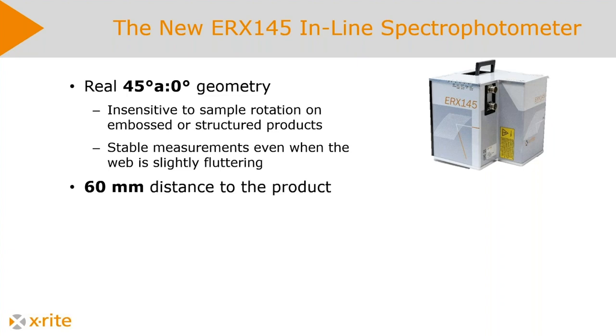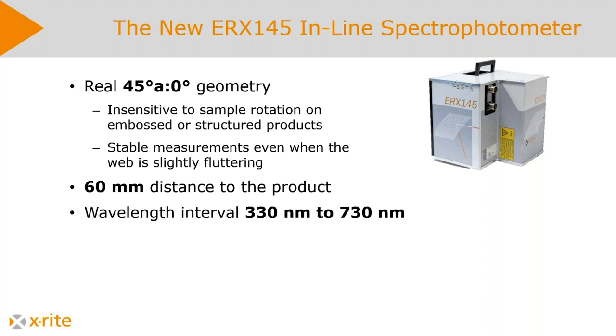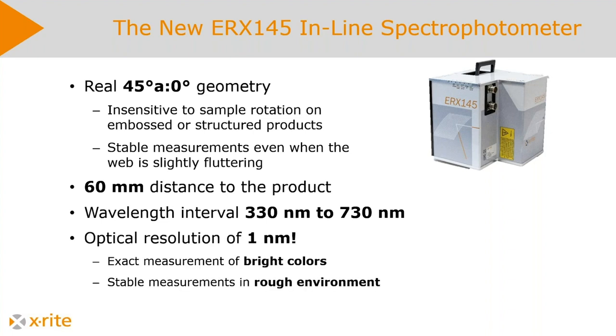We have a distance of 60 millimeters from the product to the instrument, so it's a nice space in between. We measure the color from 330 to 730 nanometers, and even more critically, we measure this in 1 nanometer resolution. Why is this so important? Well, of course, if you have a higher resolution, you can measure bright colors much more accurately, but I think the biggest advantage is that we have much more stable measurements because of this 1 nanometer. And I will show you this in the next slide.